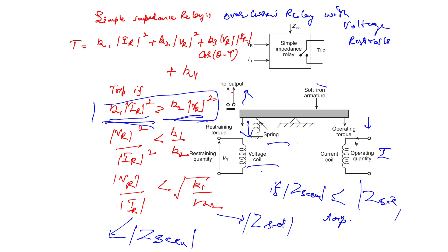Now the relay will trip if this condition is followed, that is K1 IR square is greater than K2 VR square. Similarly, as we have done in the previous case, the Z seen is less than the Z set. So the balanced beam structure implements the simple impedance relay. This is how the simple impedance relay can be represented by the balanced beam structure.